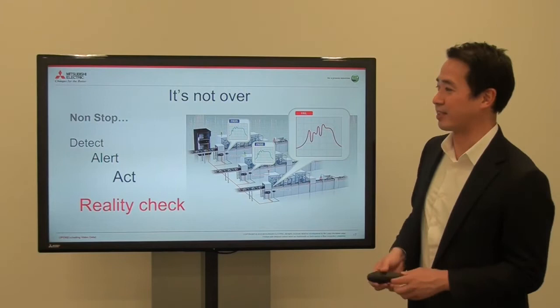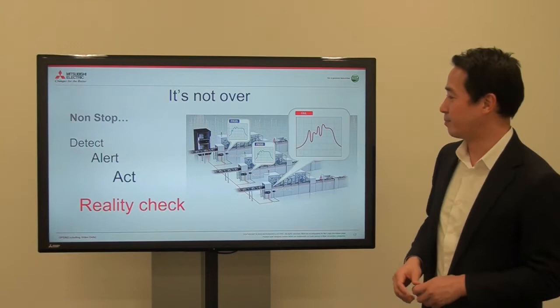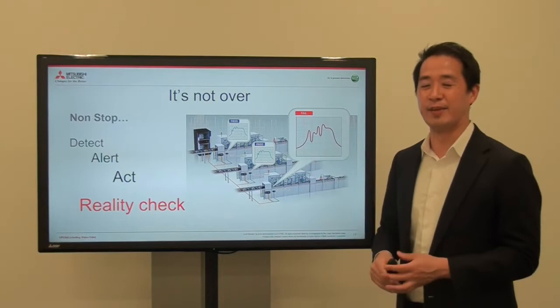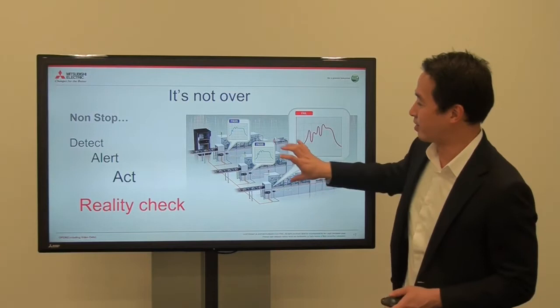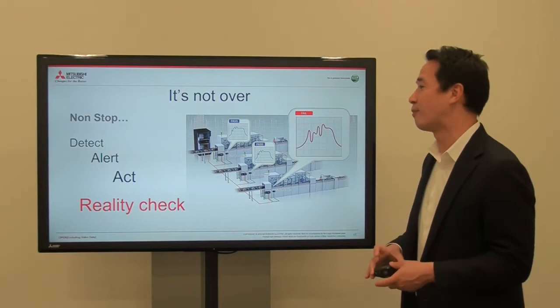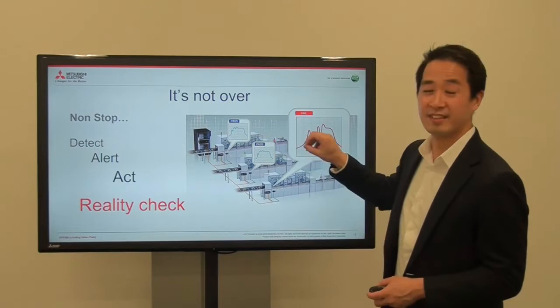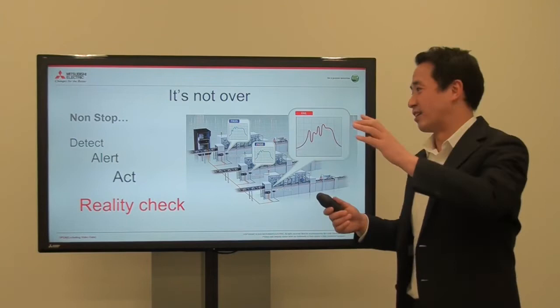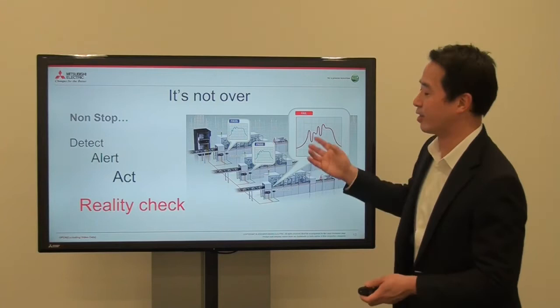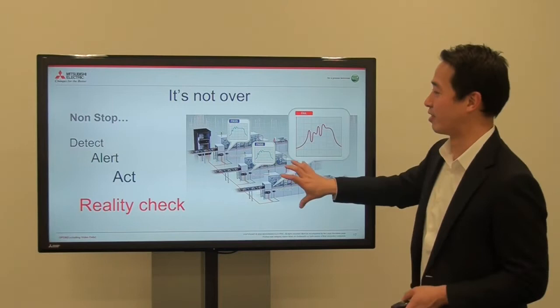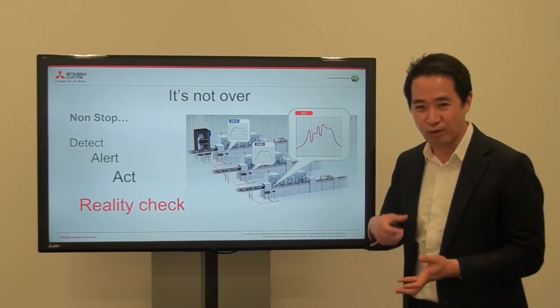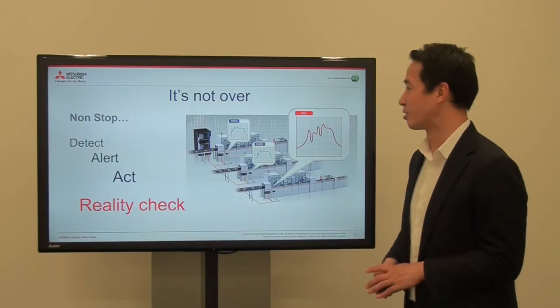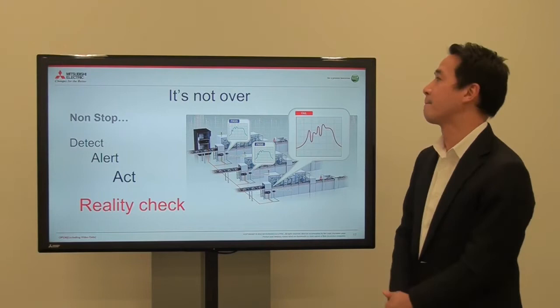Once it's finished, you can do predictive maintenance — but remember, it's not over. It works for one machine, but alerting is not enough. You should make the PLC program to stop the machine when that alert happens. Can you pass this model on to other similar machines or production lines? Yes, maybe you can copy it, but you should test again. Because even between line C and line B there might be some differences — maybe one degree diagonal — that would alter the entire data patterns, meaning the predictive formula and thresholds will differ. So it's important to take this program and test it on the other line as a reality check. If you change the product, you would have to go through the same sequence again. It's a never-ending process of refining the data and checking if it's okay.